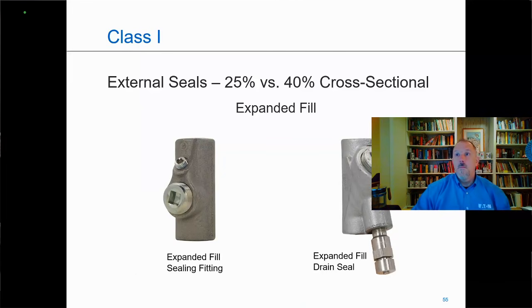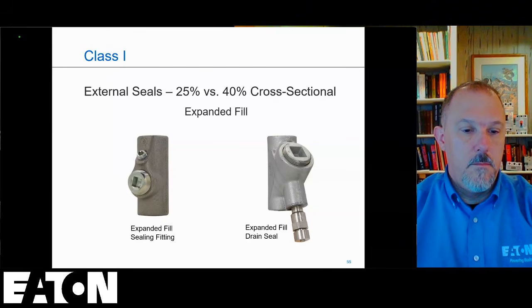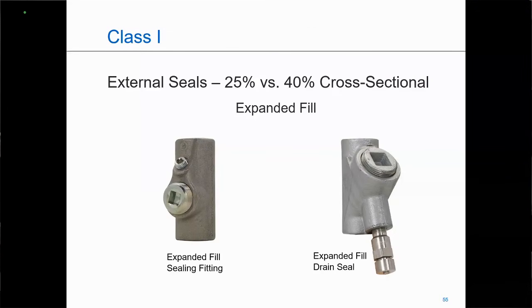This particular slide is the one we discussed, where your normal sealing fitting is a 25% cross-sectional fill, and to have an expanded fill sealing fitting, that will give you the 40% cross-sectional. These are examples of the expanded fill sealing fittings. Essentially, the hub size is the size you need and the body is bigger.